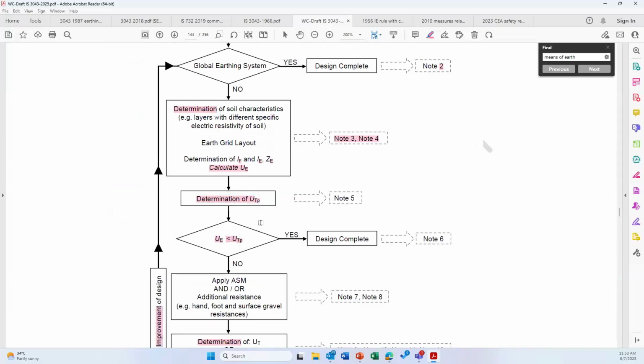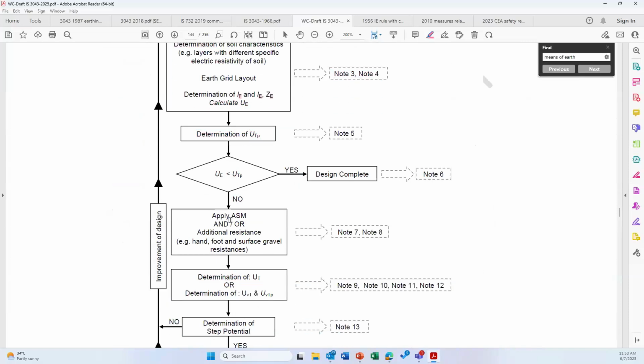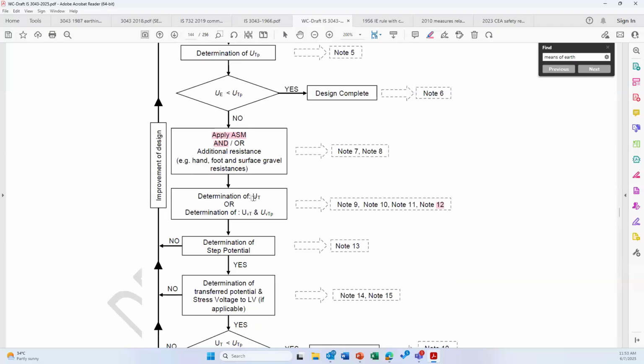If the UE is lesser than UTP, yes, design complete. That means if the maximum earth potential rise is lesser than the allowed touch potential, your design is complete because you don't get a shock. That is the idea. If the UE is higher than UTP, then you have to apply the additional safety measures, which are also explained in notes 7 and 8. Then you should determine UT, which is the touch voltage, determination of UVT, prospective touch voltage, and prospective UVTP you should calculate.